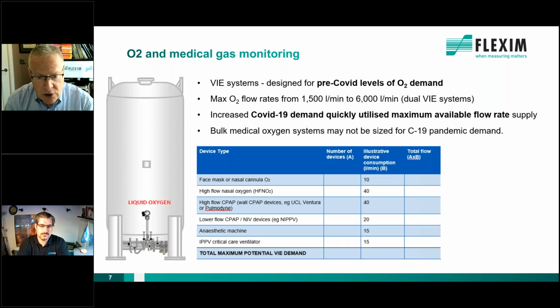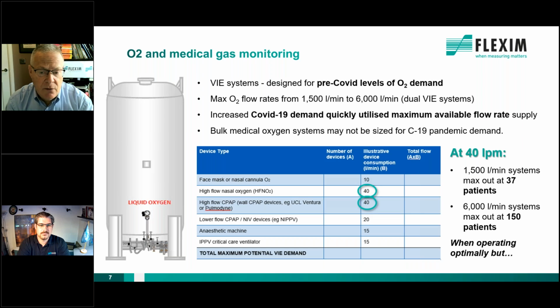Now, in days gone by, pre-COVID, systems are designed and rated to cope with expected demand. And we can see here that a typical demand for oxygen for basic ventilators might be 40 litres per minute. Now, with COVID-19, obviously things got a little bit out of hand. The number of patients was rapidly ramping up. And you can see that if we have a single VIE at 1500 litres per minute, with 40 litres per minute per patient, you're looking at a maximum of 37 patients. If we have two vacuum insulated evaporators, a 6,000 litre per minute system, you could probably achieve 150 patients.